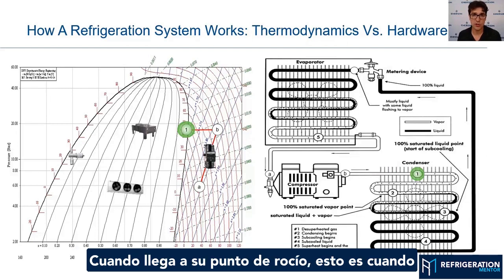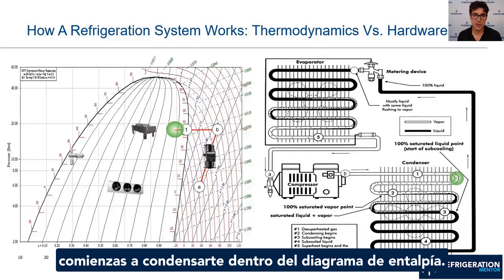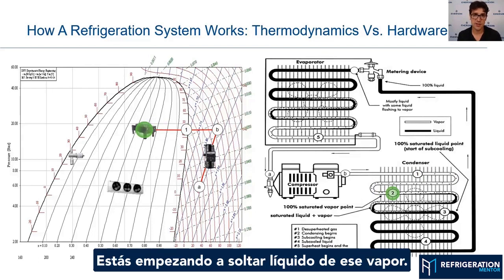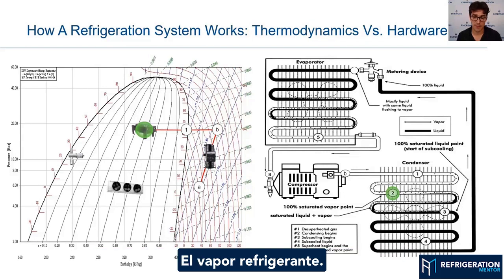When you hit your dew point, this is when you start to condense inside the enthalpy diagram. As you can see, at point 2, that's where the condensing starts. You're starting to drop liquid out of that vapor — the refrigerant vapor.